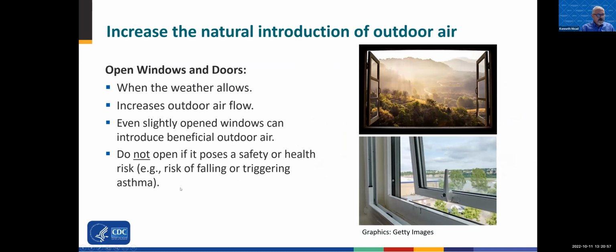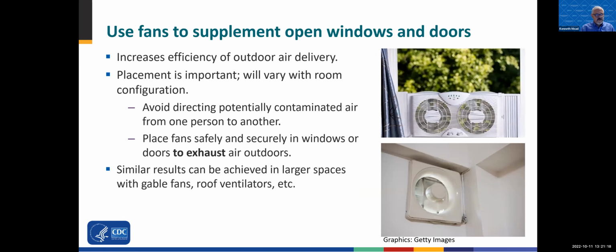It's an important concept. One of the easiest ways, if you have an emergency scenario and you need immediate relief, is to open windows and doors. When the weather allows, increasing outdoor airflow, even if it's only slightly open, can still be protective. Of course, you're not going to do so if it's going to introduce a safety or health risk. You can use fans to increase the efficacy of those open windows or doors. Use the fan in an exhaust mode. One fan in exhaust mode in one window can pull air in through all of your other windows, even if they're only cracked a little bit, and help improve the flushing of the air in that room. You can get similar results in larger spaces if you have larger fans, gable fans, roof ventilators, or whatever you may have in that space.